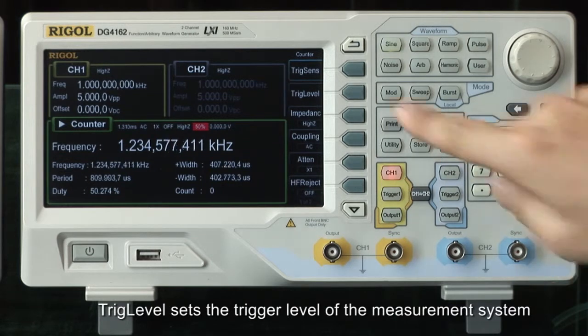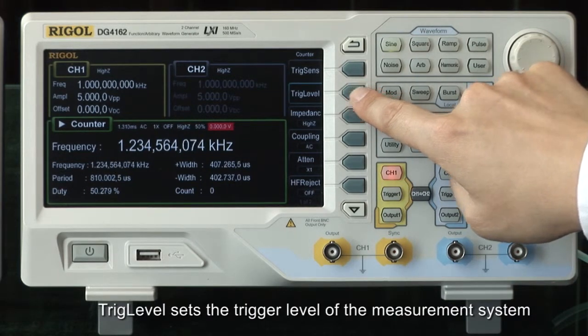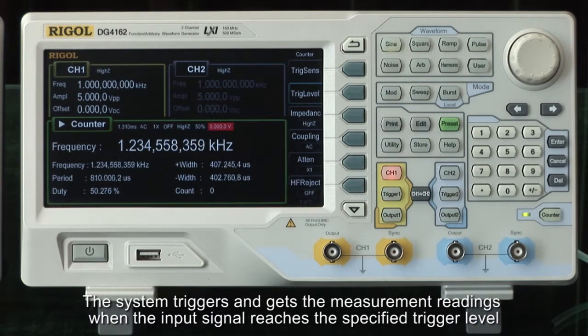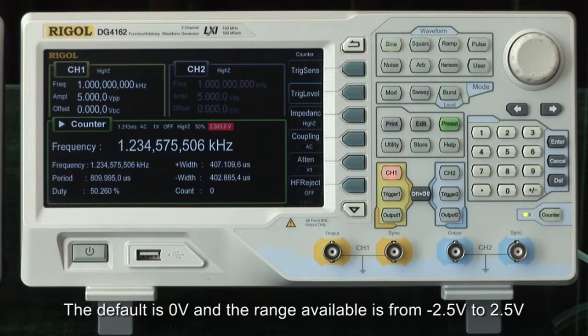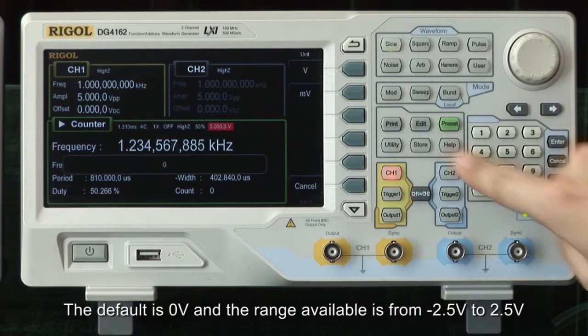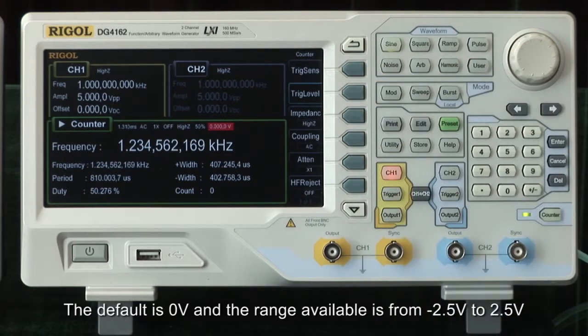Trigger level sets the trigger level of the measurement system. The system triggers and gets the measurement readings when the input signal reaches the specified trigger level. The default is 0 volts, and the range available is from -2.5 volts to +2.5 volts.